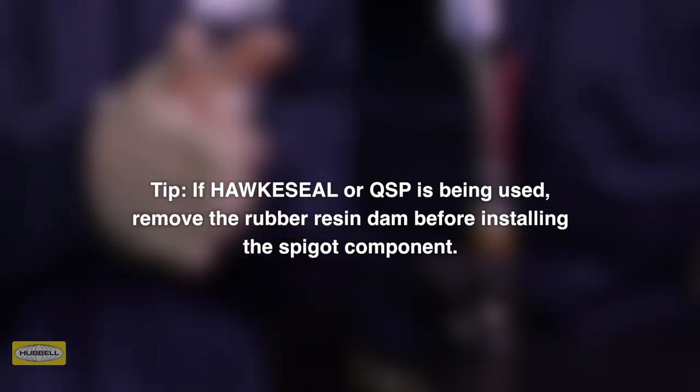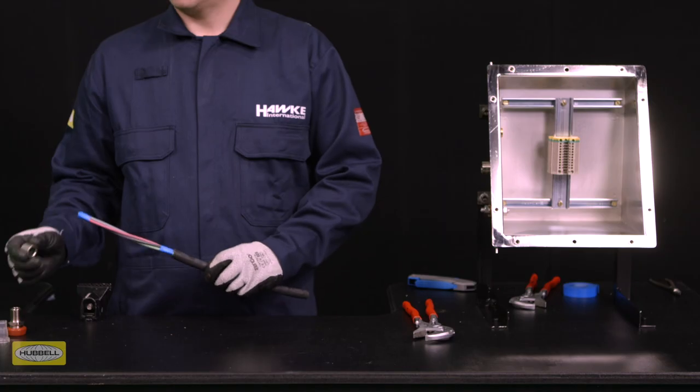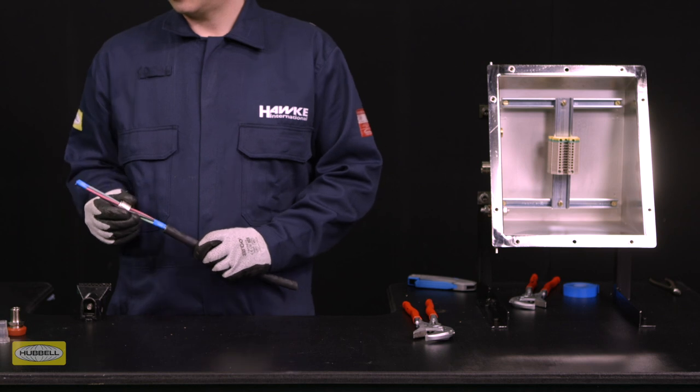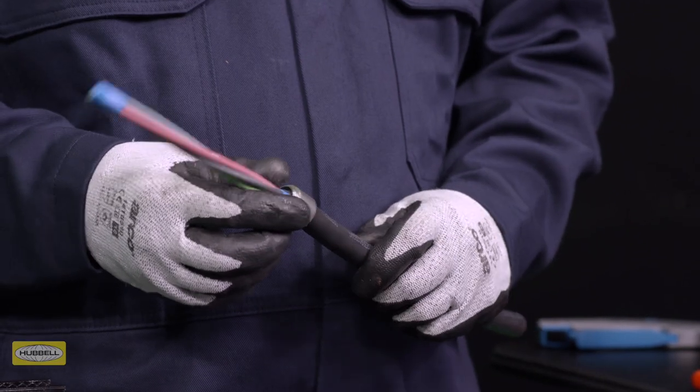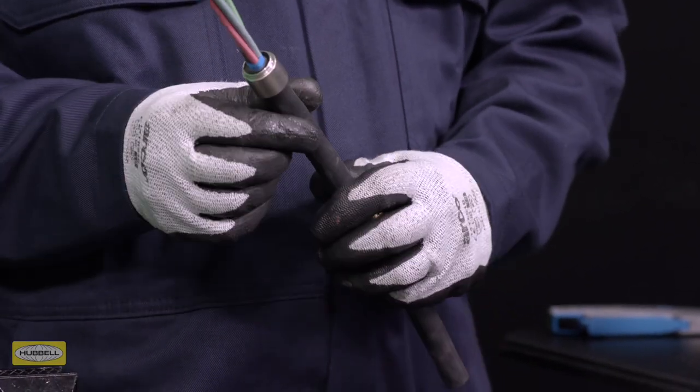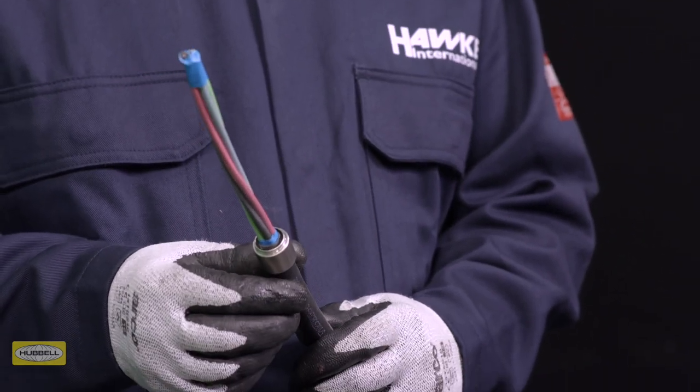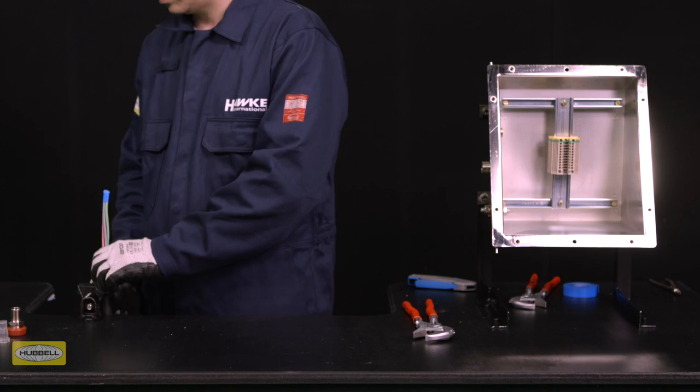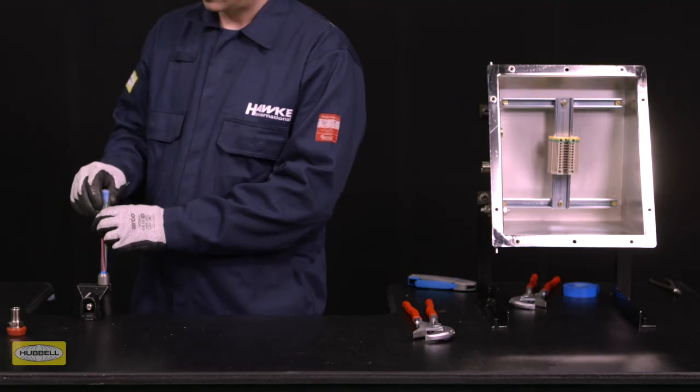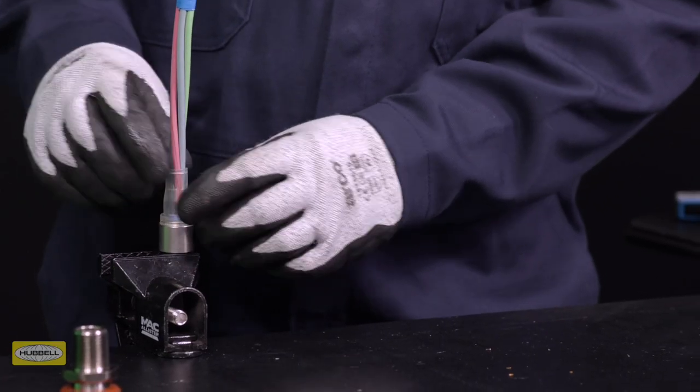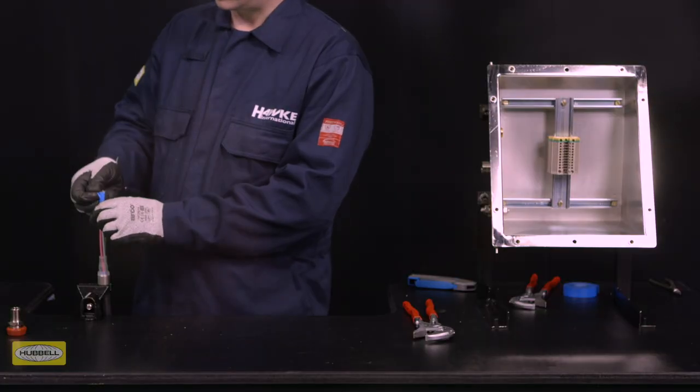If HAWKESEAL or QSP is being used, remove the rubber resin dam before installing the spigot component. Slide the spigot over the cable, taking care not to damage the rubber resin dam, until the rear end of the spigot is at the point where the inner sheath is stripped back. Fit the pot and check that the inner sheath is at the height of the pot shoulder. Your assembly is now ready for compound.